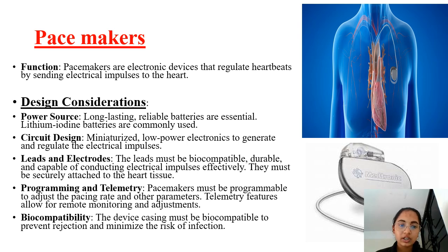So next is circuit design. Low power electronics to generate and regulate the electrical impulses. Next is leads and electrodes. The leads must be biocompatible, durable and capable of conducting electrical impulses effectively. They must be securely attached to the heart tissue.